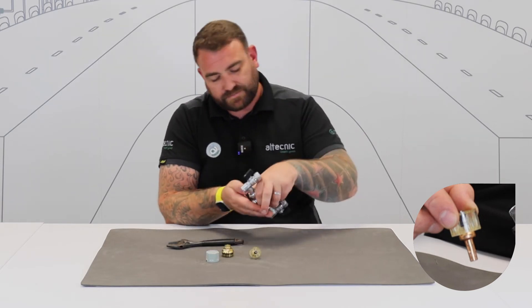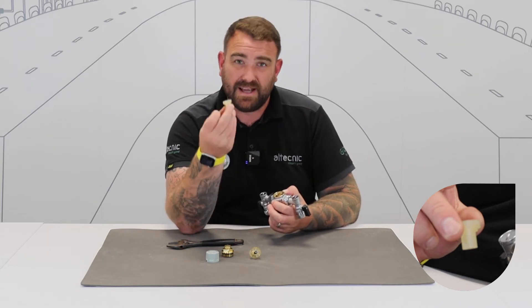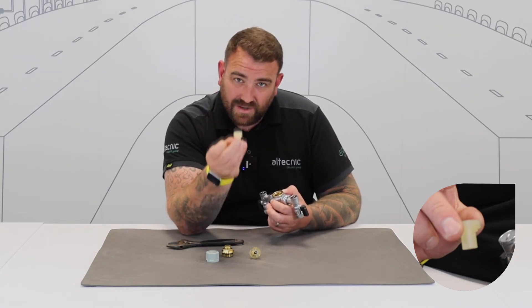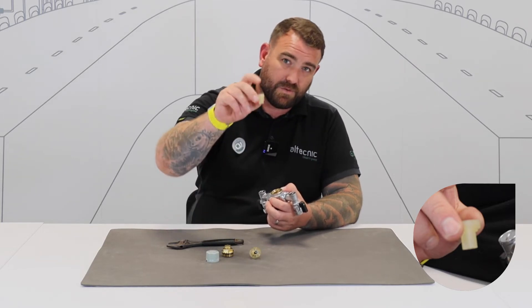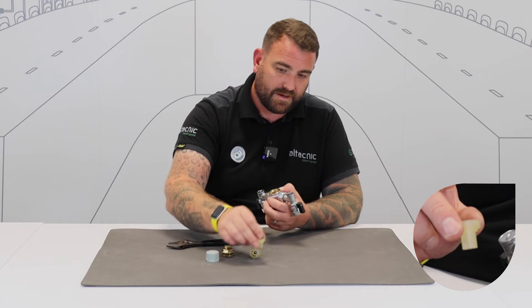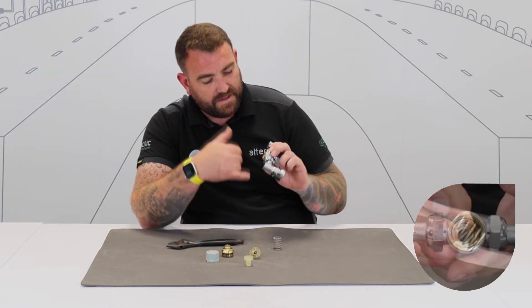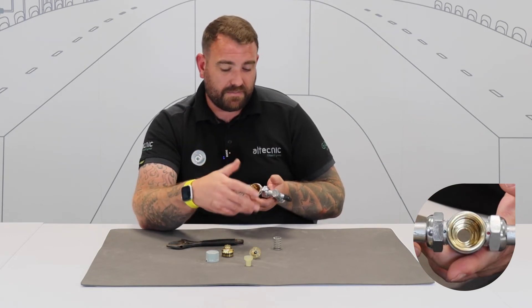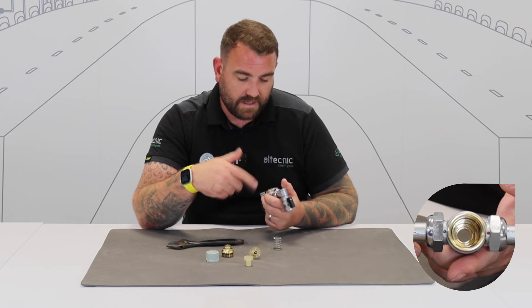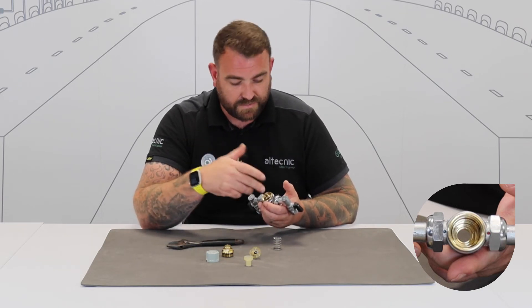The second part we have here is where the thermostatic cartridge sits — this is where the blending takes place. Again, we need to make sure that this is nice and clean, free of debris, and able to move. The thermostatic cartridge will move inside of there, so make sure that's clean, free of debris, and well lubricated. Remove the spring. Inside the valve there's an O-ring — we need to make sure that O-ring is very clean, there's no debris on there from inside the system, and also apply a nice helping of silicone grease that's WRAS approved.